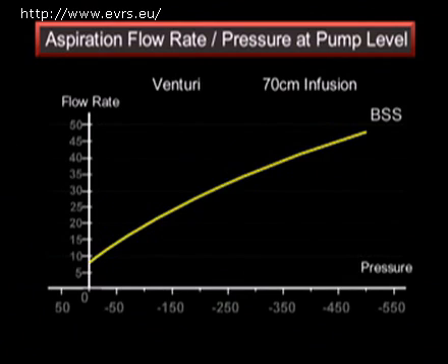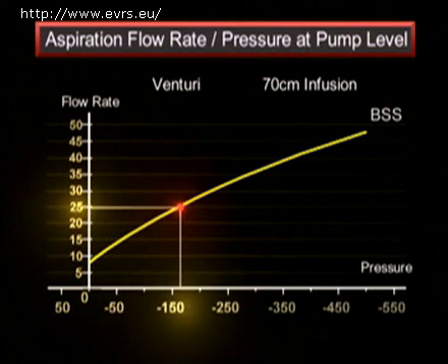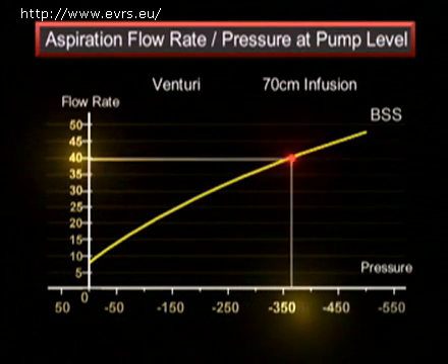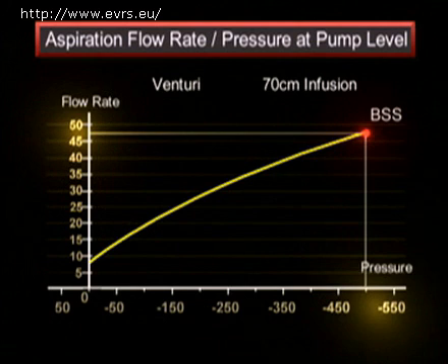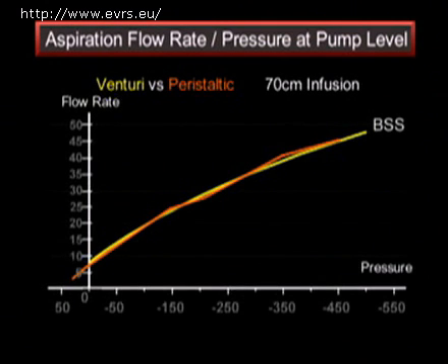The experimentation confirmed this law of physics. Using a venturi pump in BSS, a certain depression at the pump level induced a certain amount of flow. Then using a peristaltic pump in BSS, a certain flow brought about a certain depression at the pump level. Confirming the law of physics, these two curves are perfectly superimposable.